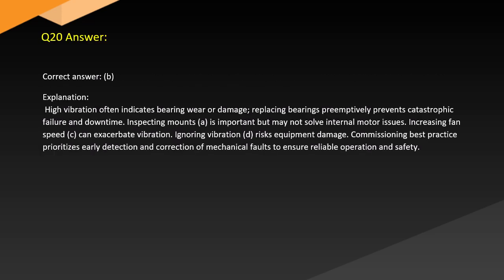Answer. Correct answer. B. Explanation. High vibration often indicates bearing wear or damage. Replacing bearings preemptively prevents catastrophic failure and downtime. Inspecting mounts, A, is important but may not solve internal motor issues. Increasing fan speed, C, can exacerbate vibration. Ignoring vibration, D, risks equipment damage. Commissioning best practice prioritizes early detection and correction of mechanical faults to ensure reliable operation and safety.